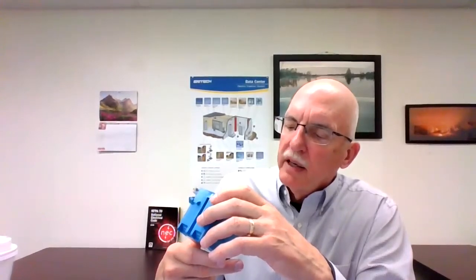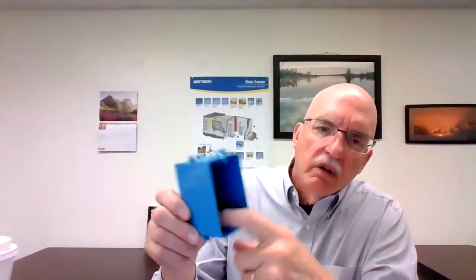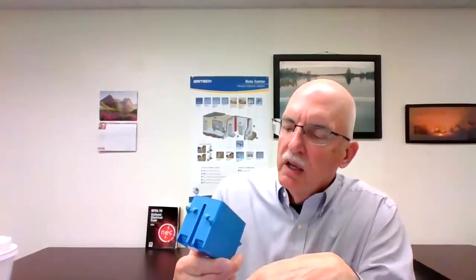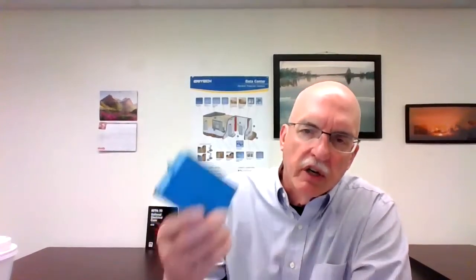One thing I want to point out is that when you are doing your box fill calculations and you refer to Table 314.16(A), read the title of that table. That table is for metal boxes. The cubic inches and allowable conductor fill is conveniently stamped right inside any of these plastic boxes. Like this Carlon box, for example, this is an 18 cubic inch switch box. And it's imprinted inside that this can handle nine 14s, or eight 12-gauge, or seven 10-gauge conductors.